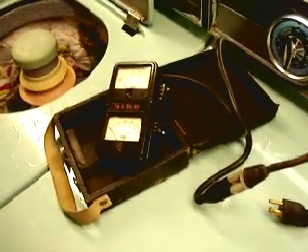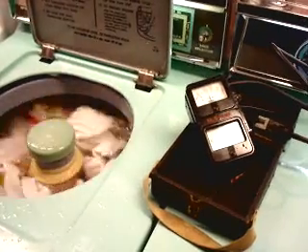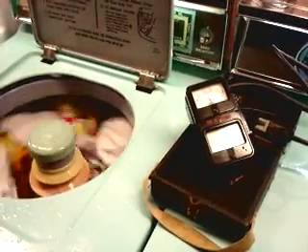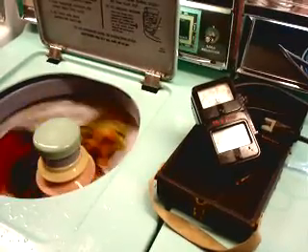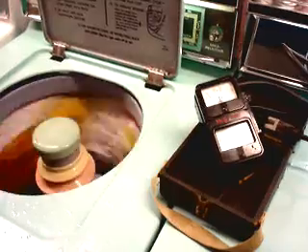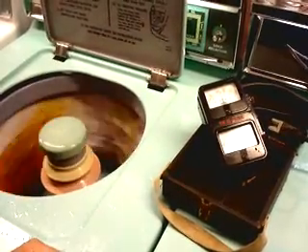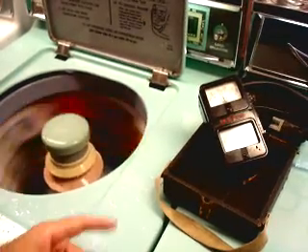Only 40 more seconds. Wonder if this Frigidaire will really suck the amps. 2,500 is what I say. And then it'll jump down when the spin, when the start winding cuts out. The start winding will have to, yeah. This is up high. Does it start to go down as it's getting faster now? No, the start winding — look.